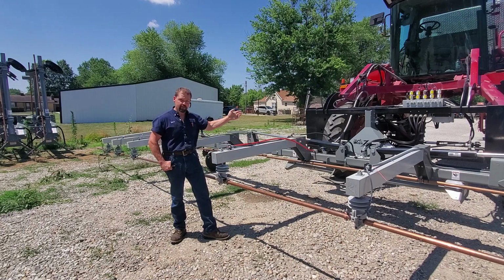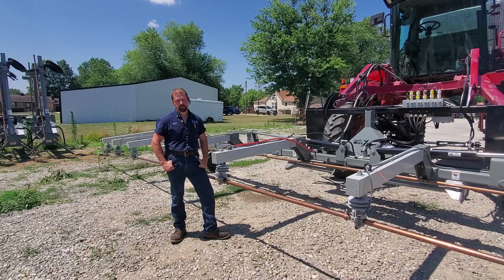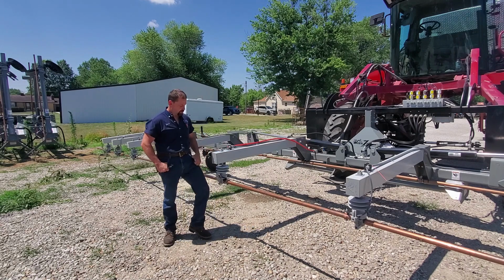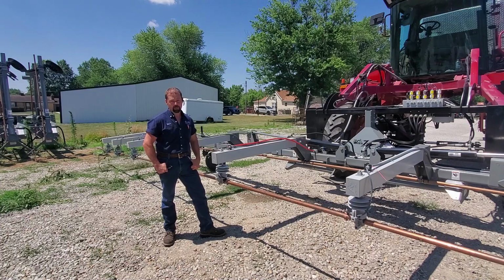So how do we find out where's the short on a 15,000 volt system? Well, process of elimination. So step number one, we go to the cart. The first part of the elimination or isolation is to remove our high voltage cable from our transformer terminal, as you can see we've already done. Basically, at that point, any errors or problems we have are isolated inside the cart.